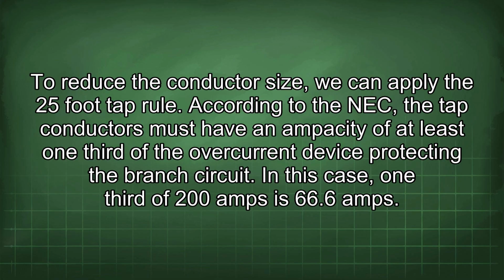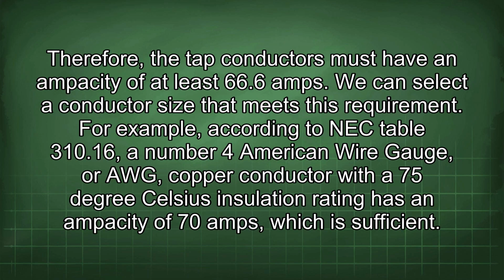To reduce the conductor size, we can apply the 25-foot tap rule. According to the NEC, the tap conductors must have an ampacity of at least one-third of the overcurrent device protecting the branch circuit. In this case, one-third of 200 amps is 66.6 amps. Therefore, the tap conductors must have an ampacity of at least 66.6 amps. We can select a conductor size that meets this requirement. For example, according to NEC Table 310.16, a number 4 American wire gauge, or AWG, copper conductor with a 75°C insulation rating has an ampacity of 70 amps, which is sufficient.